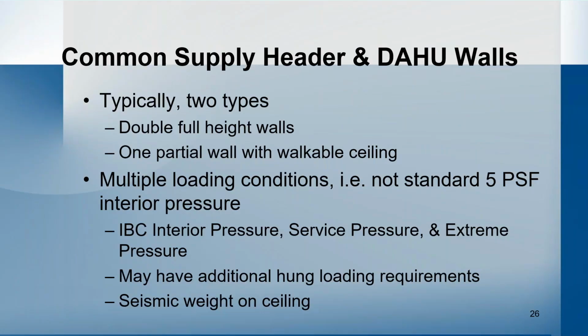I mentioned that common supply header and the DAHU walls. So what we typically see here, there's typically two types. There's either a double full height wall, or there's one partial wall with a walkable ceiling. And with that, you also have a guardrail. Your shorter wall that's not full height will have a guardrail that needs to be accounted for. And with this, we often see multiple loading conditions. So it's not just the standard 5 PSF interior pressure. What we're often given is your IBC of 5 PSF interior pressure, a service pressure, and then your extreme pressure. The service pressure is the anticipated pressure being pushed through, and then the extreme pressure is the absolute maximum that the system could possibly put through.